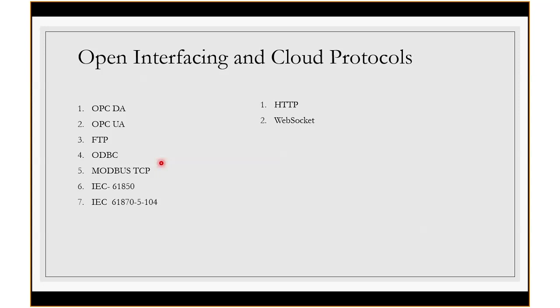So OPC DA and UA are usually used for real-time data access. Even in the OPC DA case, people use an OPC tunneler for secured data access, which is additional software. So our advice is it's better to go with OPC UA instead of DA.